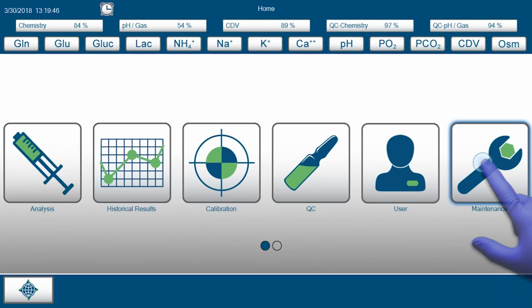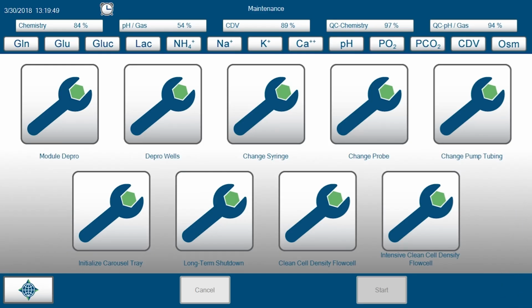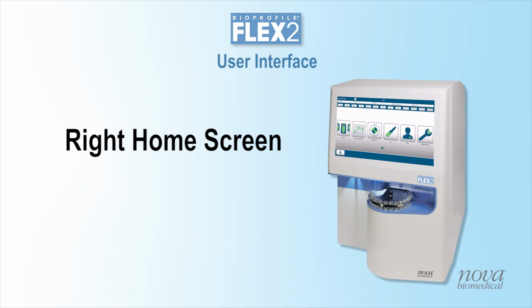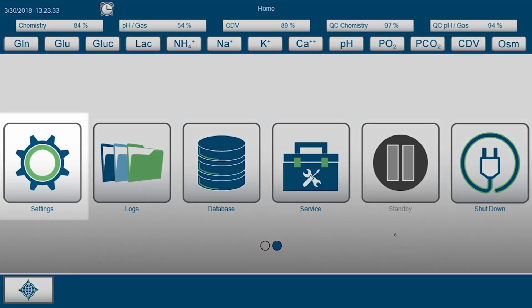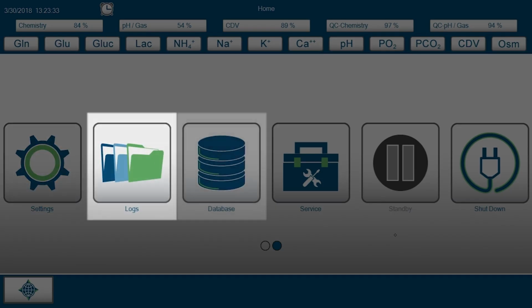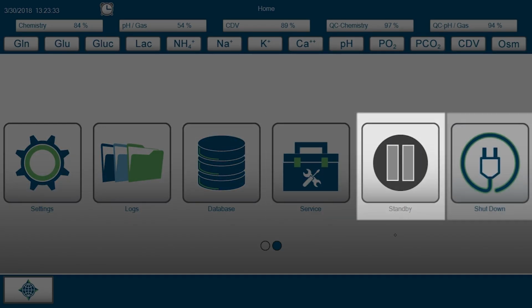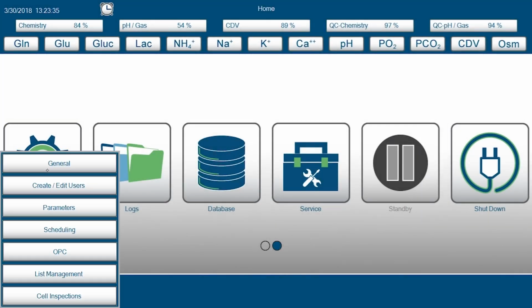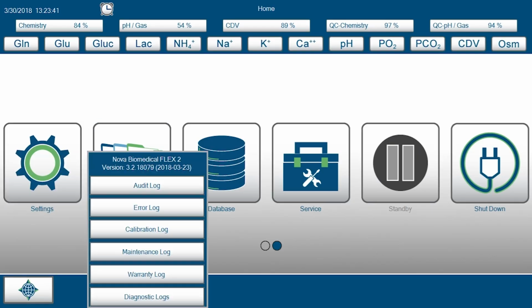The Maintenance menu allows you to perform some routine consumable replacements, cleaning functions, initializing, or shutting down the analyzer. We cover these steps in the Maintenance module of this training, so please refer to that section for more details. The right home screen includes the Settings, Logs, Database, Service, Standby, and Shutdown icons. The Settings icon allows you to change the configurations of your instrument. The Logs icon will allow you to view the audit log, error log, calibration log, maintenance log, warranty log, and diagnostic logs. You can also export these logs as needed.